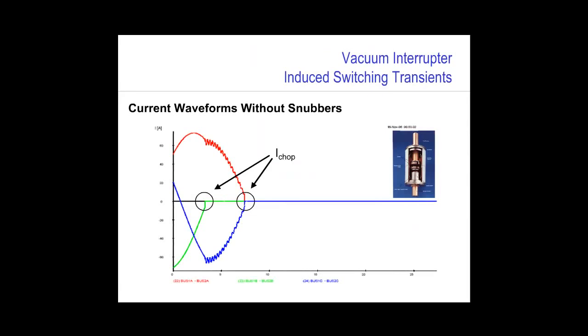After reviewing the system dynamics, the cause of the transformer failure was determined to be the proximity of the VI, or vacuum interrupter, to the first winding of the transformer. And it came down to a characteristic of the VI itself, a characteristic known as current chop. Chop current is actually a published parameter that most all VI manufacturers will offer, and it actually is the current, a fairly low value, perhaps 4 to 8 amps, in which the VI interrupts instantaneously.